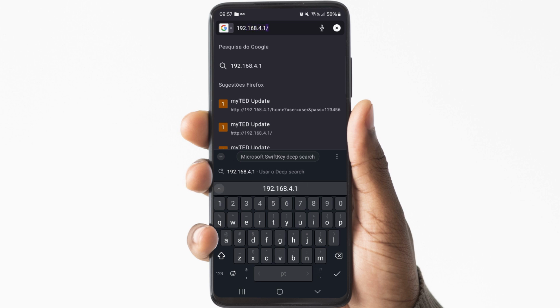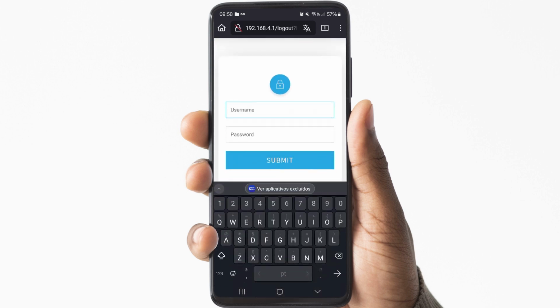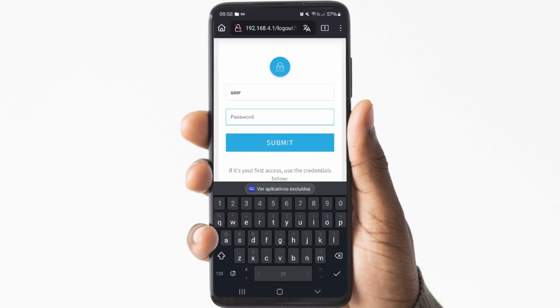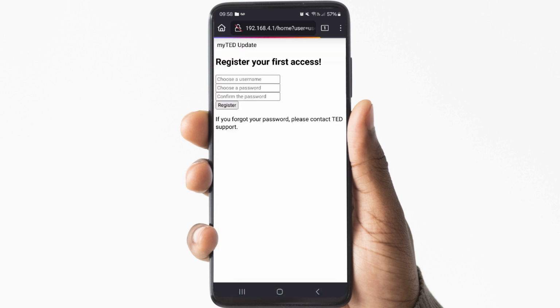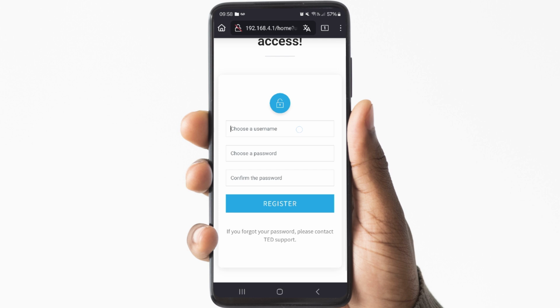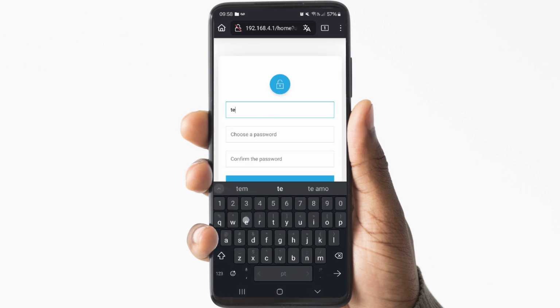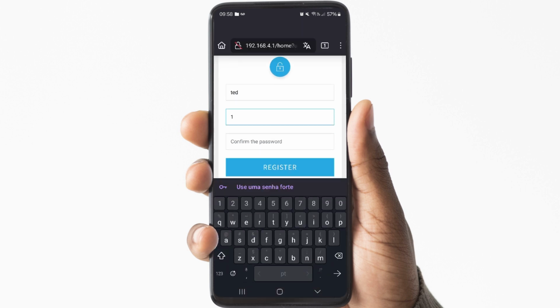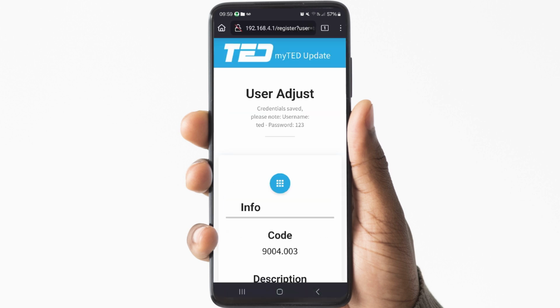192.168.4.1. A login page will be displayed to access the equipment. If this is your first access, use the user admin and the password 123456. At this point, a new window will load asking you to register a username and a new password. Choose one of your preference and complete this action. Log in with your new user. The Equipment Properties and Settings screen will be displayed.